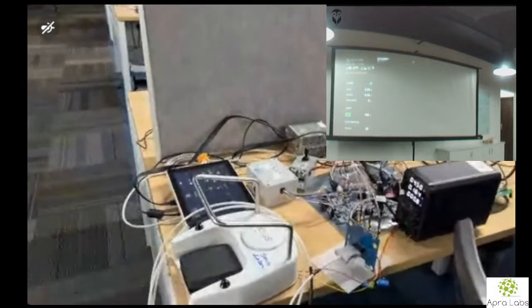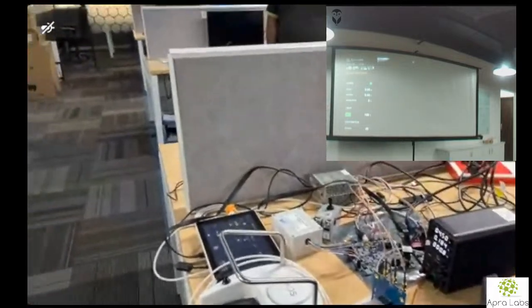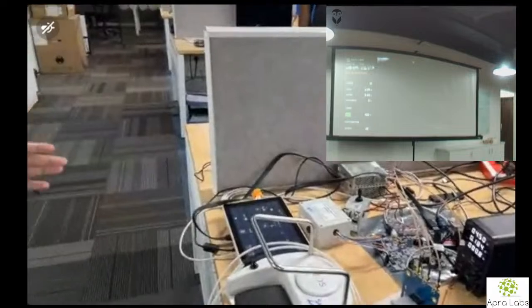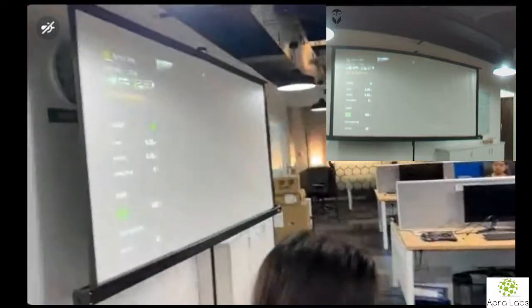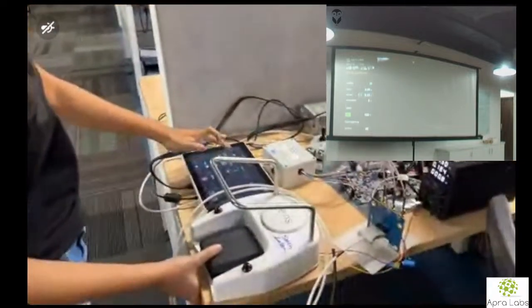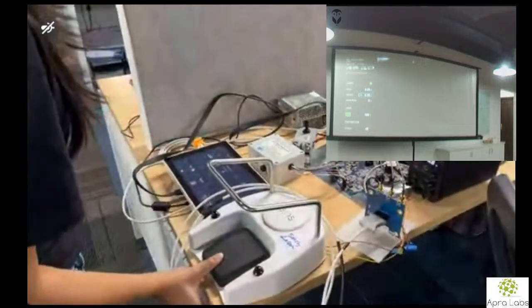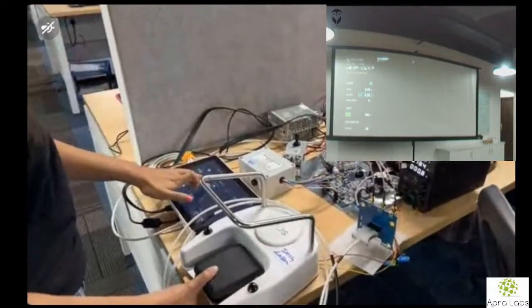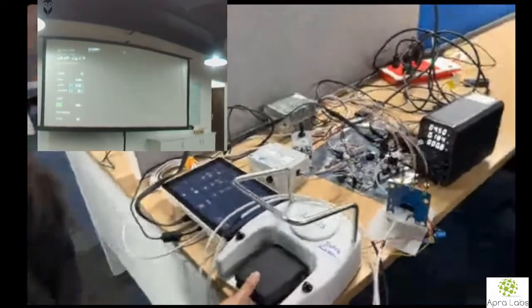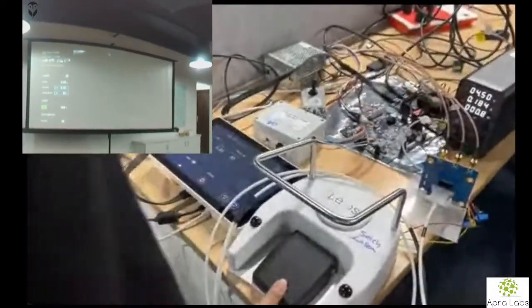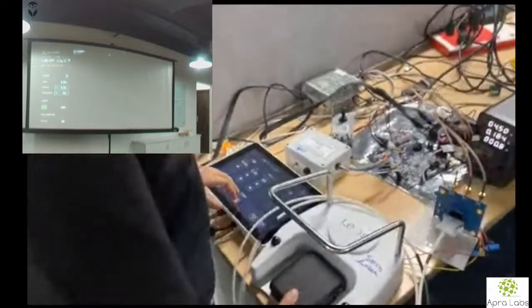Laser power right now is 0.05 and duration is 0.05 seconds. So for that duration only, the laser will be fired and then it will not be fired anymore. You can increase the duration. You can increase the aiming intensity, like how strong the aiming beam should be, and then you can fire it.